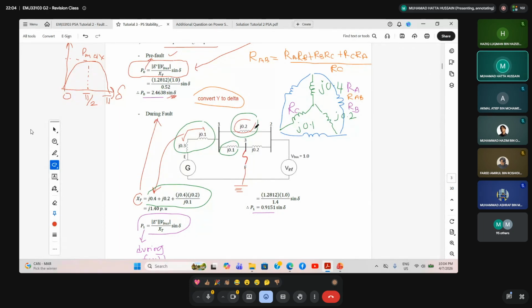This path cannot be used, because the current flow from the generator goes to bus 1, then to bus 2, then supplies to V infinity. For the lower line, it goes to bus 1, to bus 3, and then to the ground, not to the fault itself. But it cannot go to J0.2 here, which is the line connected from bus 3 to bus 2.